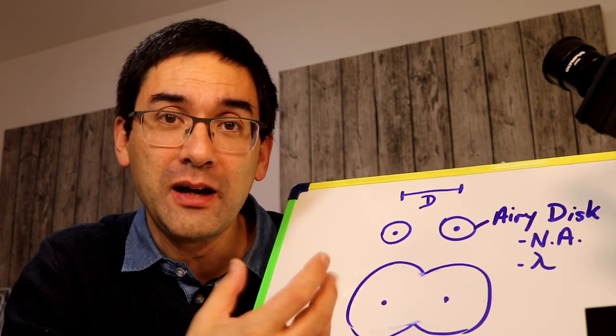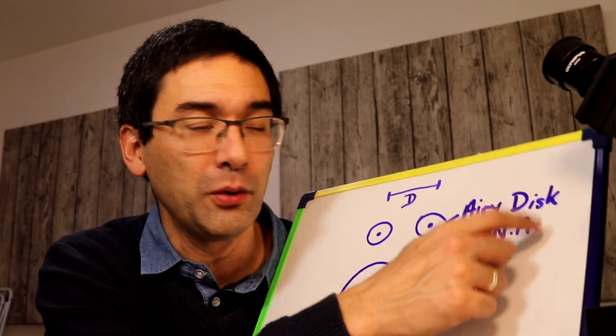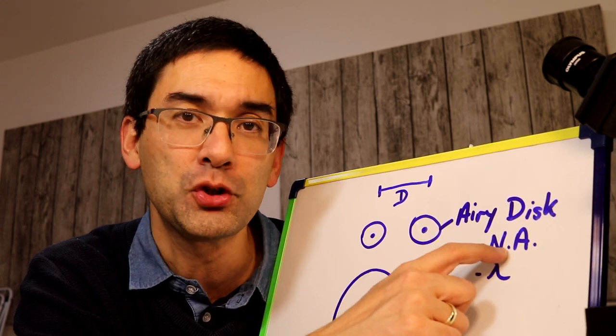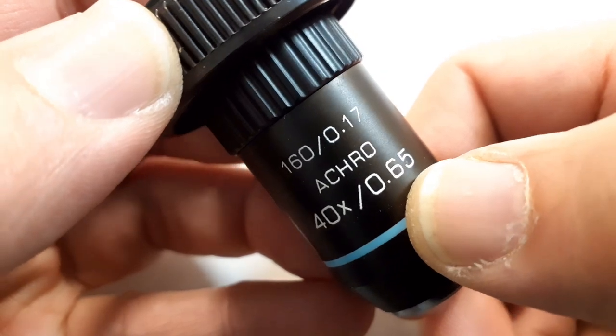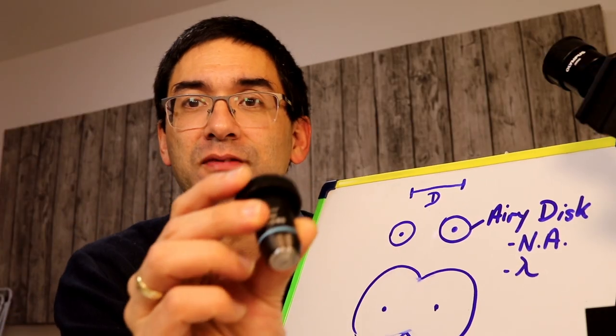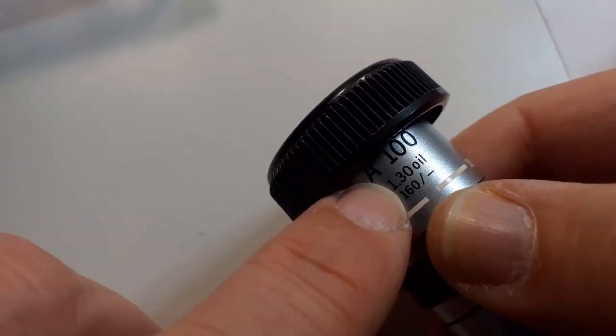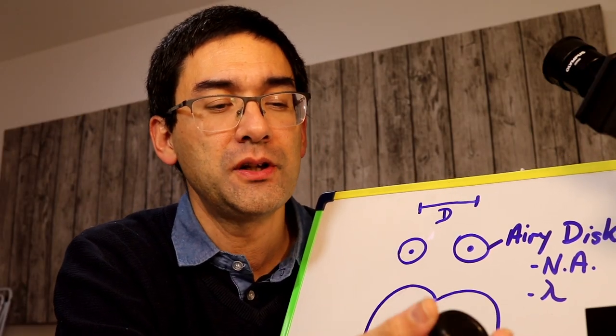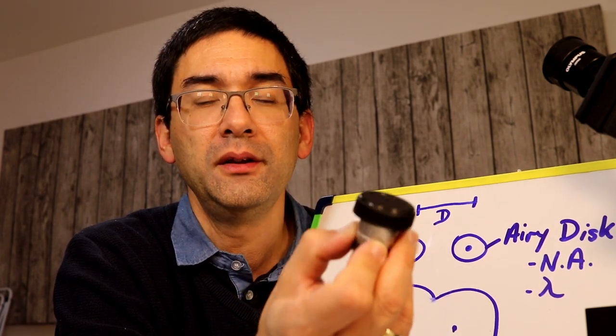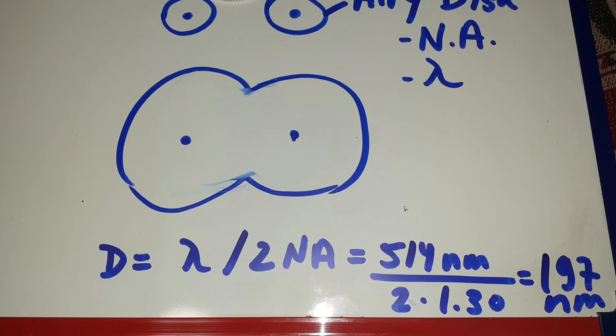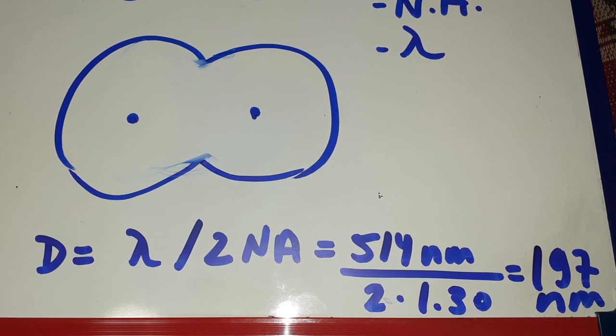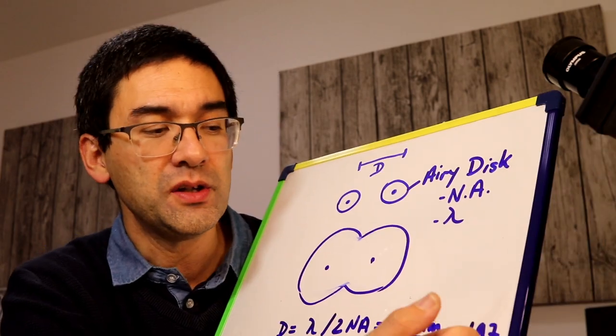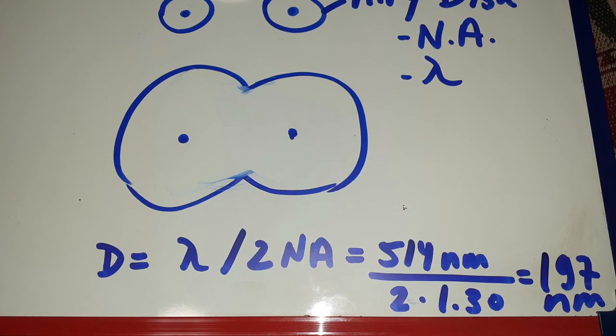Down here I've got a formula. How can you calculate the resolution? Forget the formula itself — the more important things are the two variables: the numerical aperture of the objective, which is printed on the objective, and the wavelength of light. This objective has a numerical aperture of 0.65, and my oil immersion objective has a numerical aperture of 1.3. Using green light at 514 nanometers, the resolution limit comes out to 197 nanometers — around 200 nanometers.